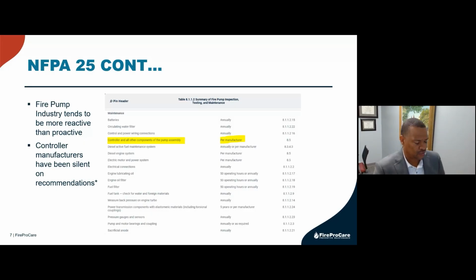The other thing I want you to remember is our industry tends to be reactive rather than proactive. What I mean by that is, from the controller standpoint or from any component in the system, we don't change parts on a regular interval to make sure the system is always in tip-top condition. We just never have. We wait until there's a problem, and then we jump on board, expedite, and spend thousands of dollars to get someone on site to repair and put the system back in place. It could be $5,000 a day for fire watch, and if you don't know what that means, they literally place a fire truck outside that facility, just in case there is a fire, until the system is back up. Very expensive, and we should definitely be looking into some type of preventive maintenance situation to help with that, so that the system has a consistent readiness status on that controller, without worries that something isn't going to work.